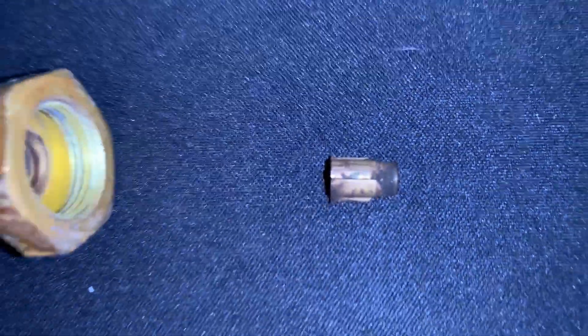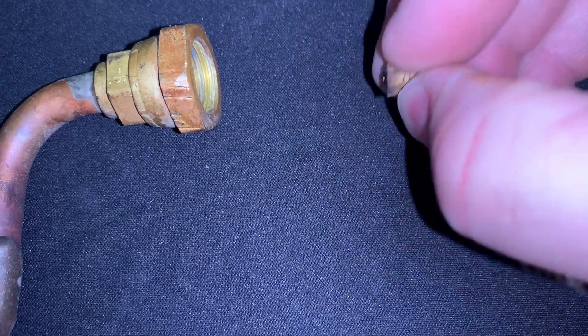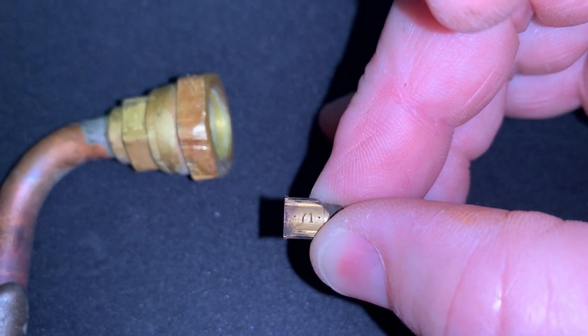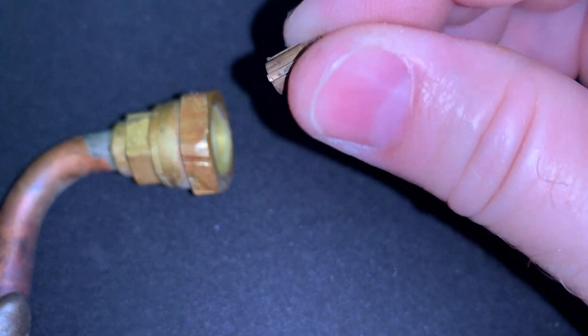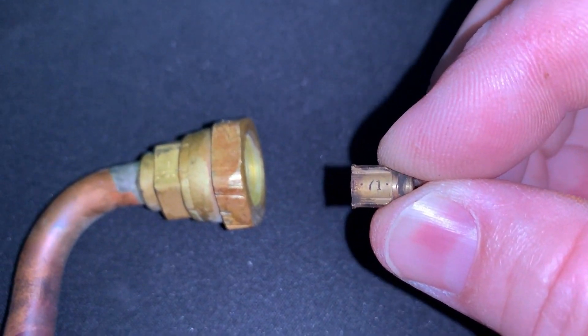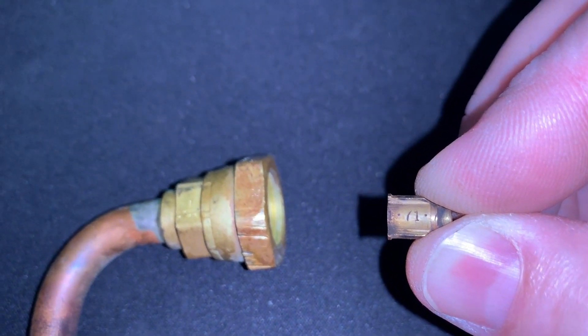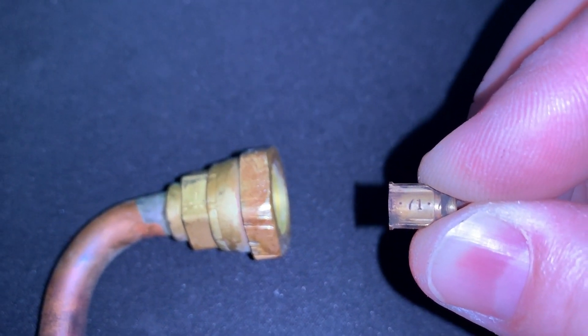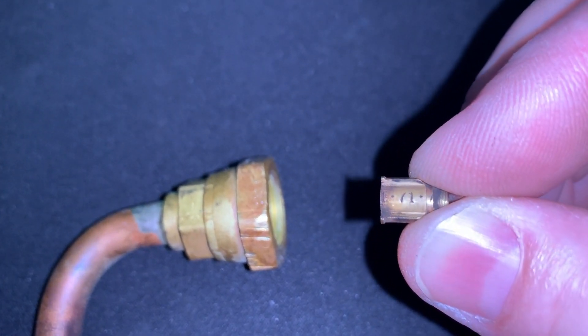When you're looking at this — I'm going to try and zoom in — there's something you need to know. You can see some writing on there. It's very small and hard to see through the camera, but you'll see a number like 71. Your HVAC technician may refer to it as a 71 or 76 or whatever the size is of the orifice. That is the size of basically the ID going through. Usually that orifice size is dependent upon the tonnage rating of the system. Mine's a 3-ton system and the 71 is in the ideal range; it can go all the way up to 76 for a 3-ton system. It's actually 0.071, but they just stamp 71 on there.